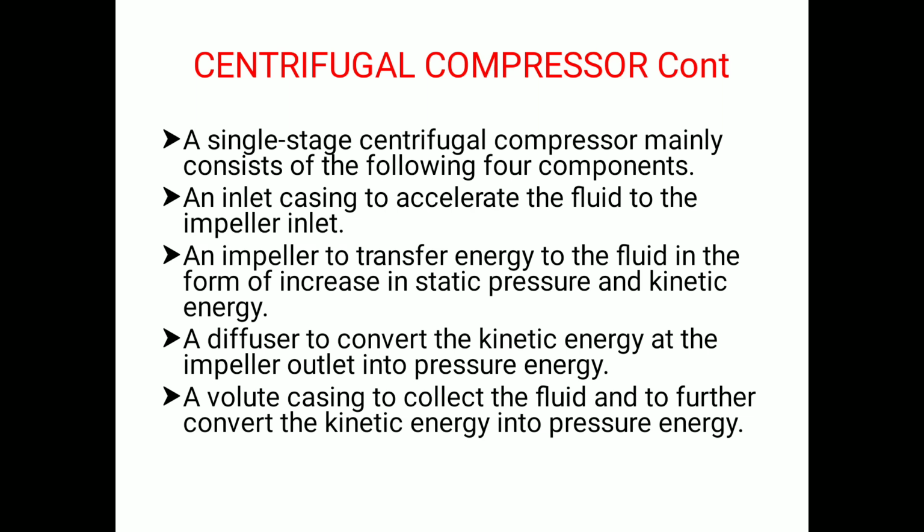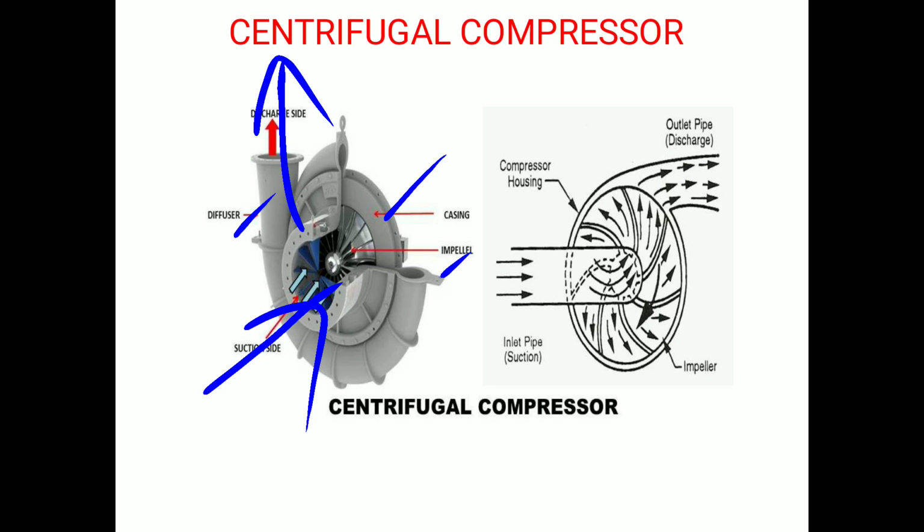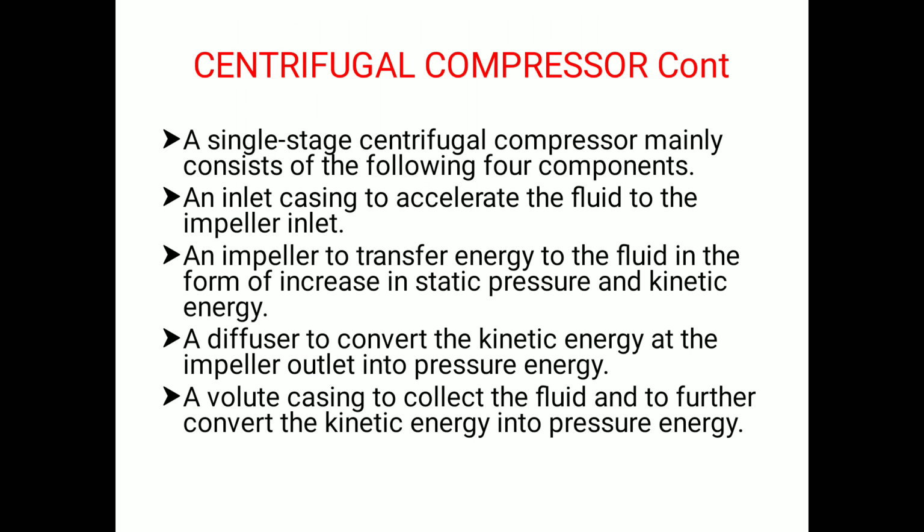And you can see there is no such complicated things like valves, pistons, cylinders, and connecting rods, etc. Therefore, the working life of the compressor is more as compared to the previous one, that is the reciprocating one. And these kind of compressors, the centrifugal compressors, are not practically used below the loads of 50 tons, which means you can't use this compressor below the load of 50 tons. 50 tons is a minimum one.